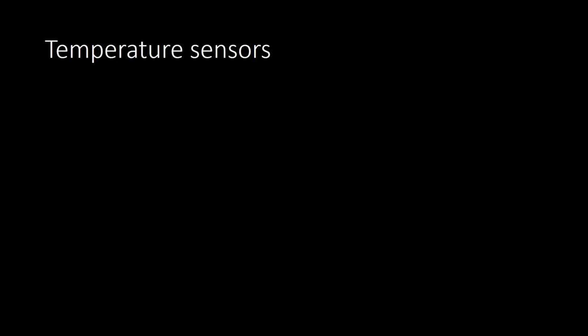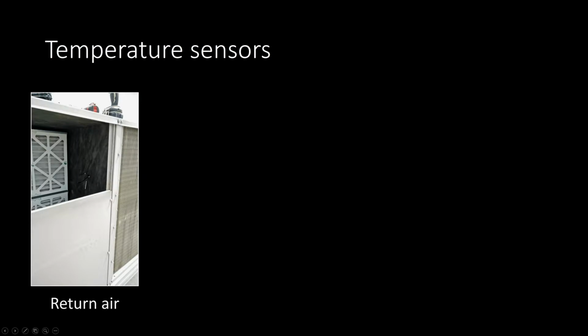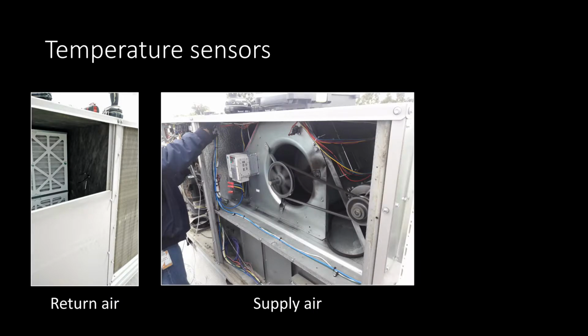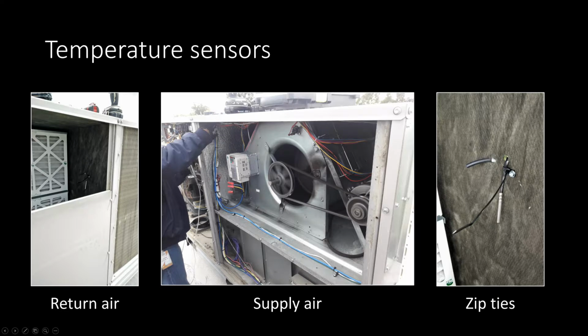Temperature sensors should be placed in 2 locations. Return air duct coming from the building before the air filter and economizer if present, and supply air duct just after the blower. Use zip ties and sheet metal screws to ensure moving air does not displace the sensors.